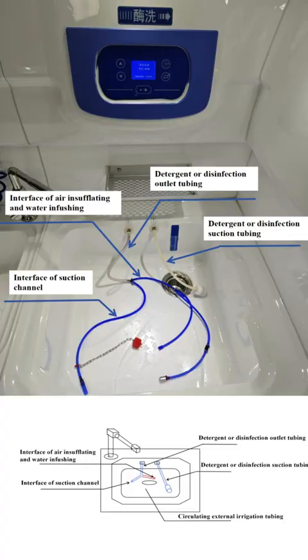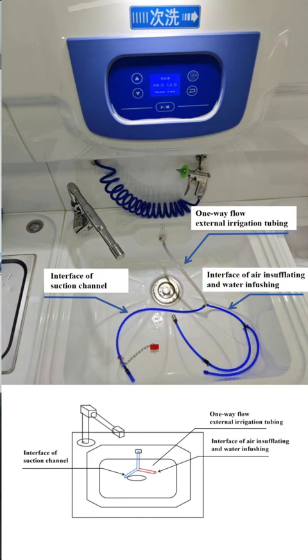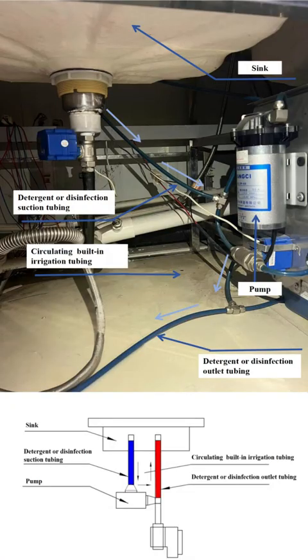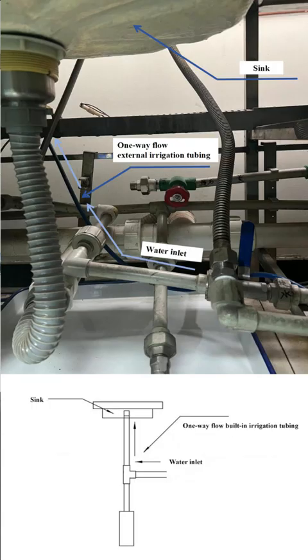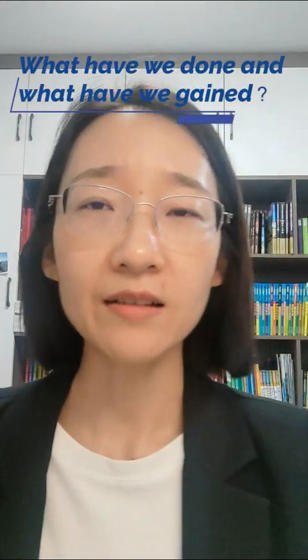The external irrigation tubing is short, removable, and disinfected, whereas the built-in irrigation tubing is slender, non-removable, and not disinfected. Thus, we identified that the potential reason for the failure of endoscope disinfection was the contamination of the built-in irrigation tubing. What have we done and what have we gained?